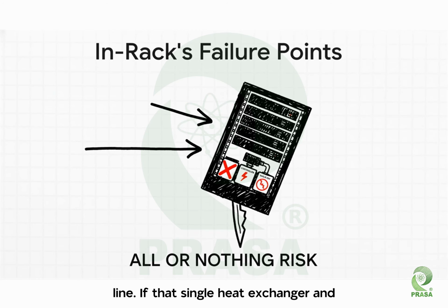So here's the bottom line: if that single heat exchanger in an in-rack CDU fails, your entire rack of servers goes down. If its single control system has a glitch, your rack goes down. If one of its valves fails, I think you get the picture. Those dual pumps can't do a thing to save you. The entire rack's operation is balanced on a razor's edge.